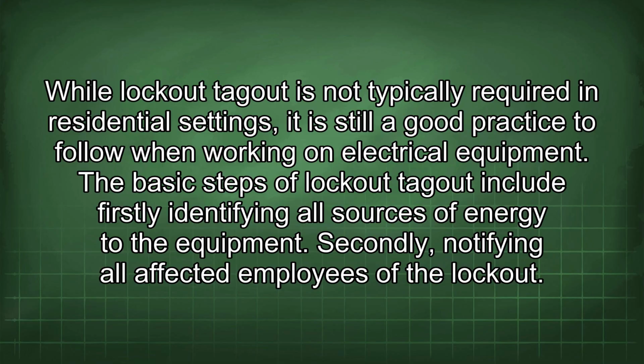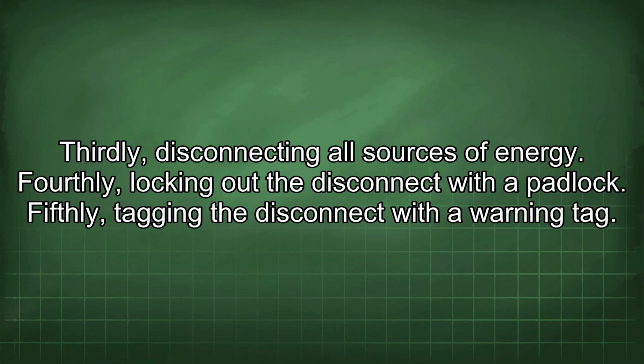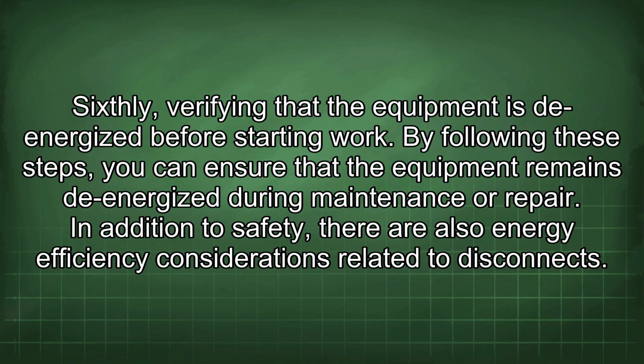Secondly, notifying all affected employees of the lockout. Thirdly, disconnecting all sources of energy. Fourthly, locking out the disconnect with a padlock. Fifthly, tagging the disconnect with a warning tag. Sixthly, verifying that the equipment is de-energized before starting work. By following these steps, you can ensure that the equipment remains de-energized during maintenance or repair.